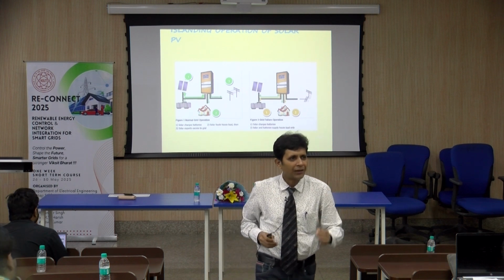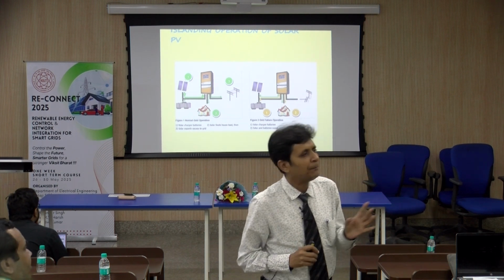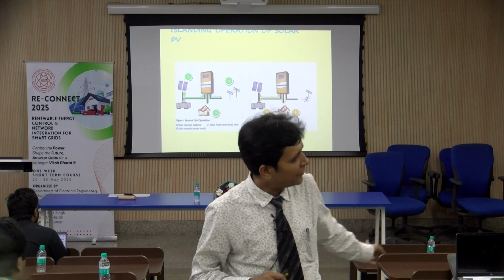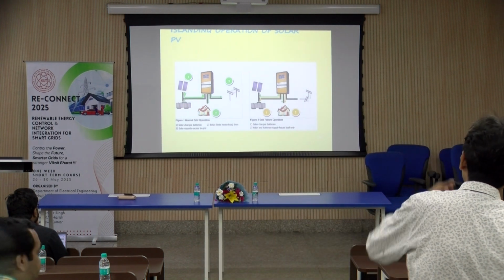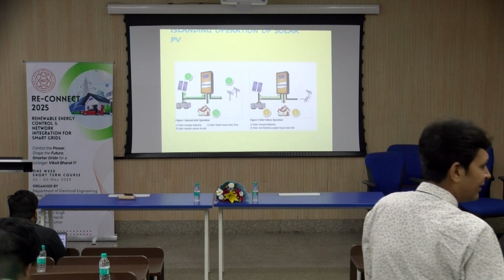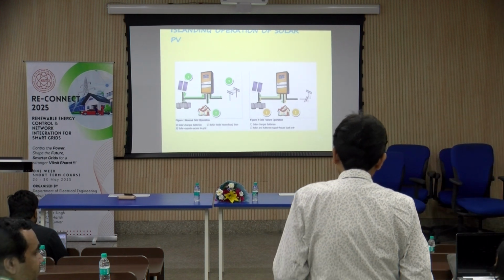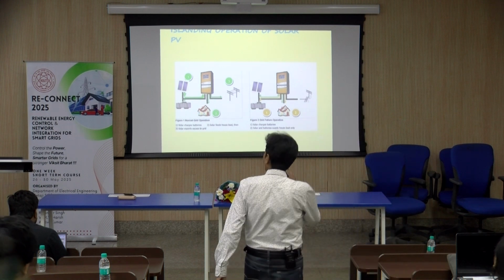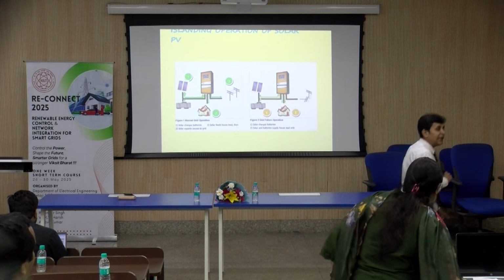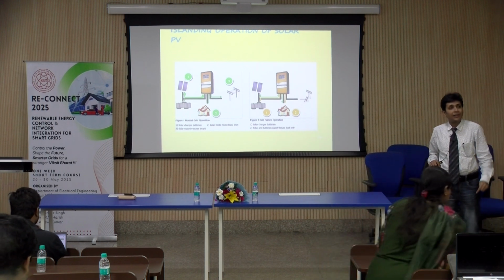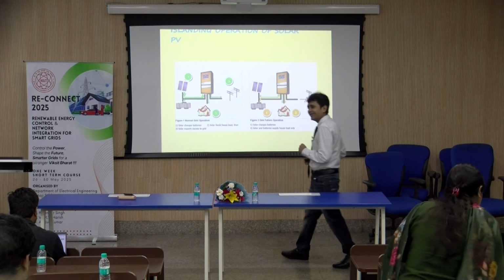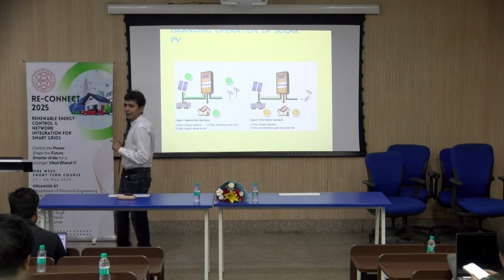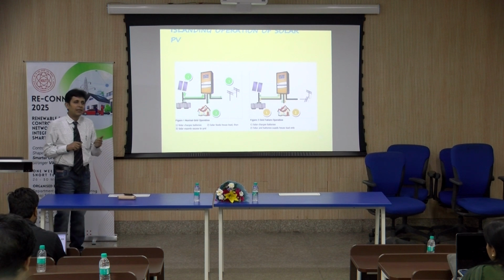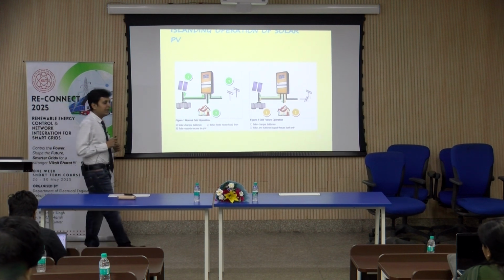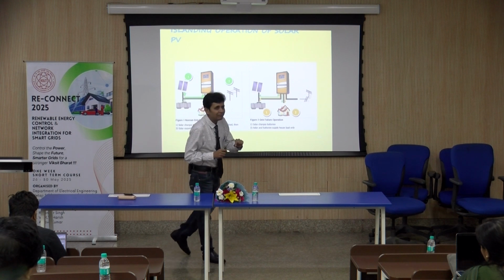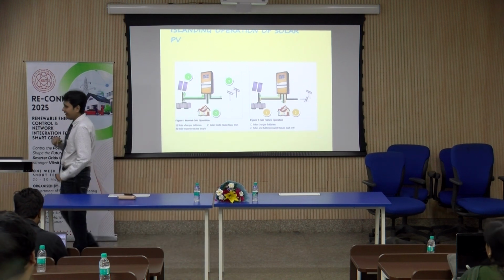There is a problem in the network. Still you are generating power. What is the consequence of that? And why is it not allowed as per the regulation in India, in the world? What happens if you do generation in the islanding mode? That power may go back to the utility system and the persons who are doing the maintenance may get a shock. That feature is mandatory for the inverters you are purchasing. That is called anti-islanding protection system of solar.